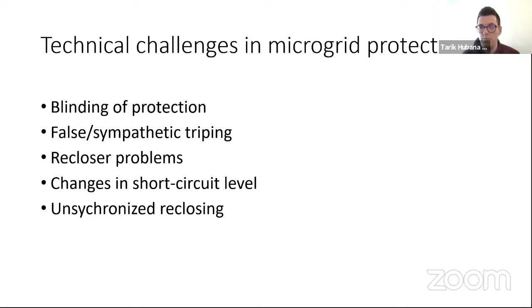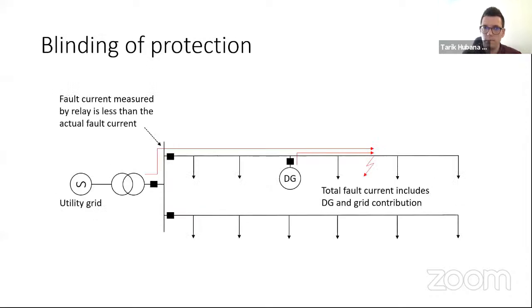We already talked about different challenges in the microgrids, and we said that the control of the microgrid is one big part of the problem. But another more sensitive part of the microgrid challenge is the microgrid protection, since it comes to the safety of the operation and the safety of the people and the personnel in that part of the system. So when it comes to the microgrid protection, there are 5 characteristic technical challenges. These are the blinding of protection, the false sympathetic tripping, the recloser problems, the changes in the short circuit level, and the unsynchronized reclosing. So we will go briefly through each and every one of these.